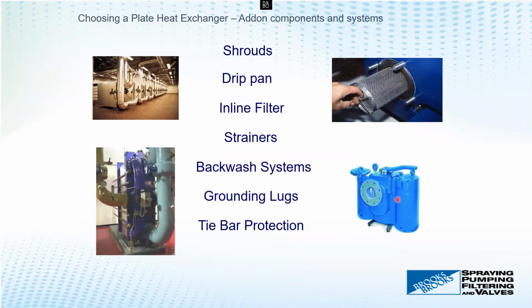We can do inlet filtering, strainers, you name it - all sorts of options, grounding lugs. Tie bar protection is also very common - we put PVC wraps on tie bars so that when they get bashed into with forklifts, or exposed to dust and grease over time, they stay greased and protected so they can actually do their job when it's time to do maintenance on your heat exchangers.